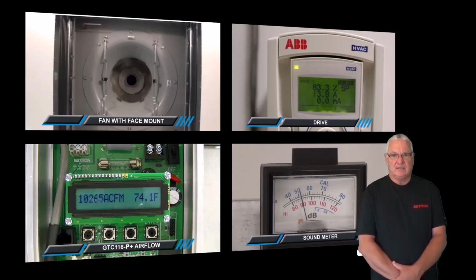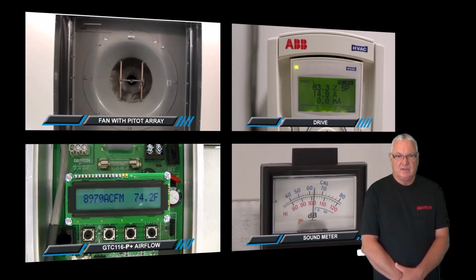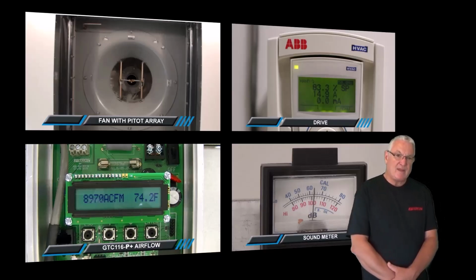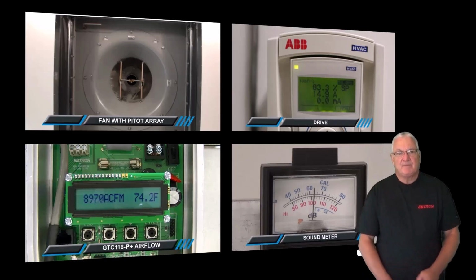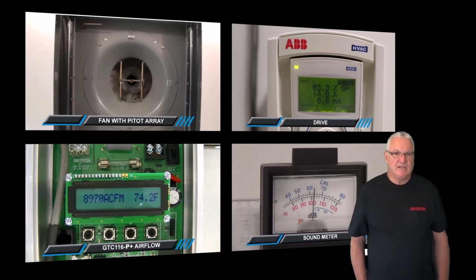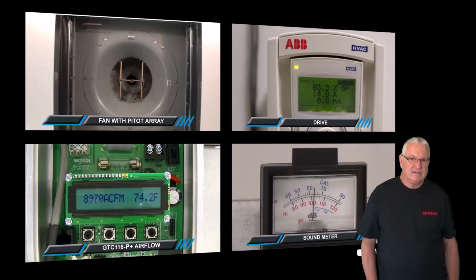The drive current draw is no different. The flow's basically the same and the sound level's no different. Okay, we put a pitot array in just to kind of show you the problem that they have with plenum fans. The problem with plenum fans is if you put something in the throat of the fan, small throat of fans. And so here you see a pitot array.